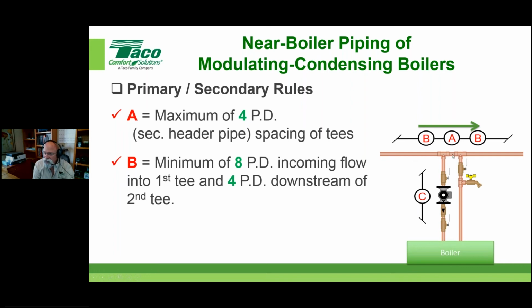Remember, as close as possible here, but downstream, since we've already done the job we were meant to do by getting this water mellowed out - I'll show you what I mean by that in a minute - once we've done that, we only need about 4 pipe diameters on this second side as a minimum.